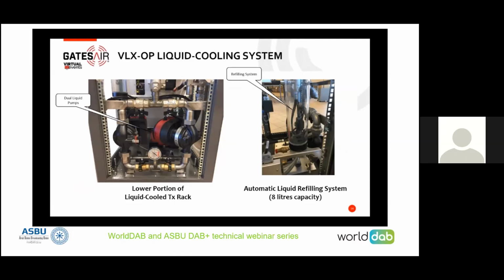And those power supplies are hot pluggable and removable, which is something to really understand. Some places you have to send it back to the factory for repair. Now the pumps, in contemporary design, can be located in the transmitter cabinet. They're very compact and low energy consumption. We'd see these are connected using stainless piping and brackets, appropriate shutoff valves and gauges and so forth. That has dual redundant pumps so that either pump could carry the load.